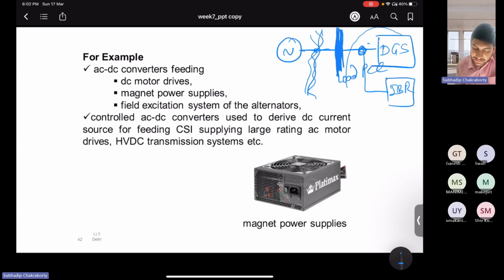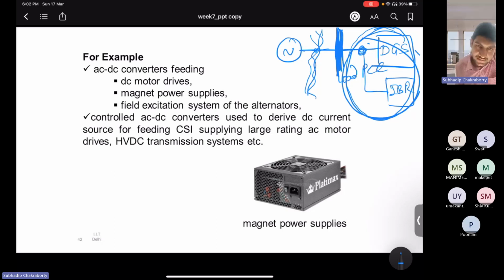Now, from your perspective as a microgrid operator or a system operator, the maximum possible thing you can do economically is to push power to, or take power from, the grid at this point at unity power factor. That is the best you can do. You cannot control this whole system, right? So the only thing you can do is maintain the power factor at that load PCC. After that, it will be distorted only because many systems are connected. But for your system, your grid operation is not affected. That is what I am telling.